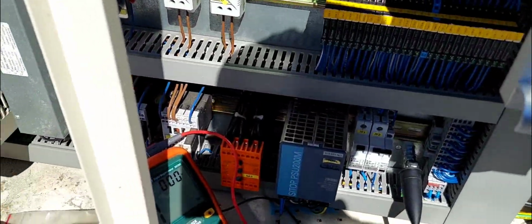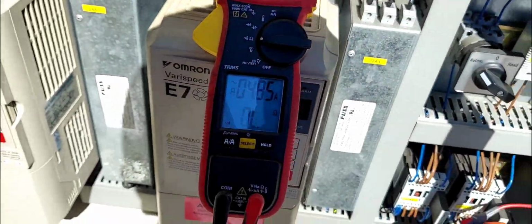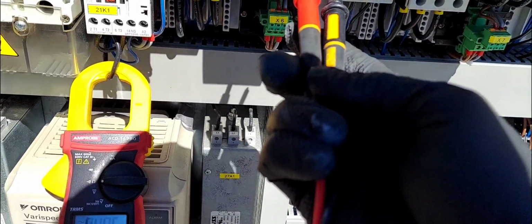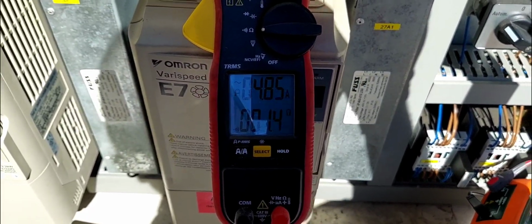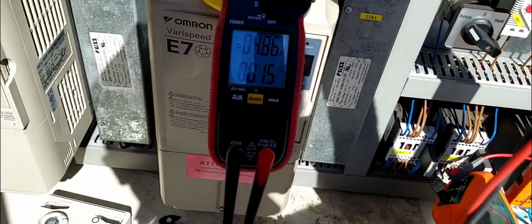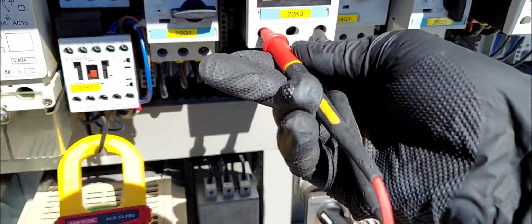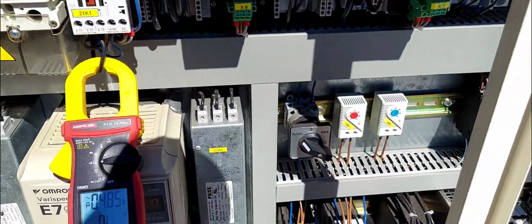One thing I didn't do, which I should have done, is this here. So I'm in continuity meter right here. What you want to do with this test as well is test the motor winding for continuity, because this confirms that all three wires go through to the compressor, and there are no broken wires and no open windings. So electrically this compressor is fine.